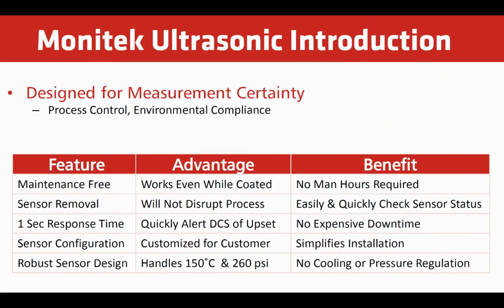Our sensor configuration is very customized for the application. We can make the sensor length custom. We can have custom valve to insert it or a custom flange welded to the probe. It just all comes down to us taking a look at the custom application need. It simplifies installation. It will just be turnkey at that point when they receive it.